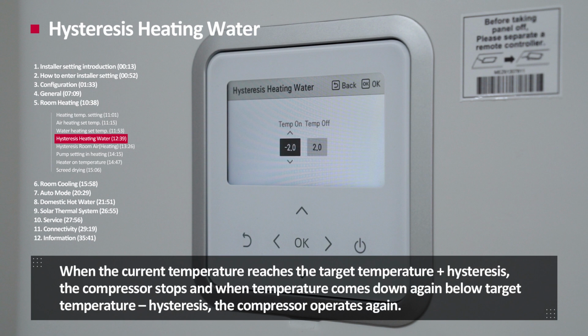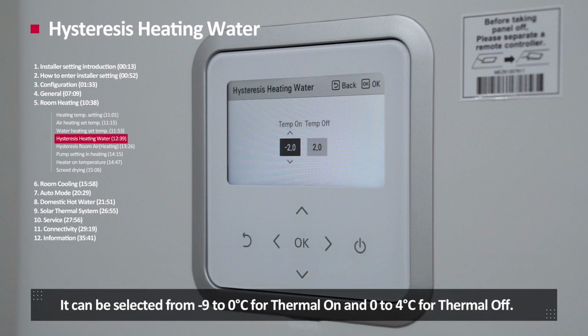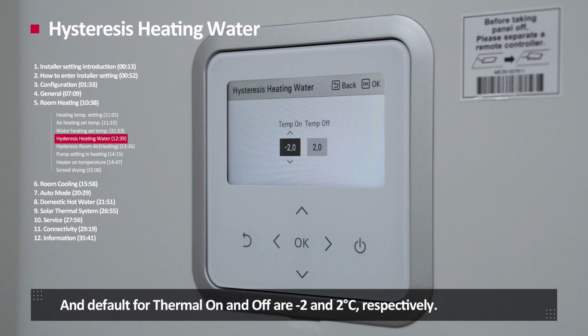When the current temperature reaches the target temperature plus hysteresis, the compressor stops. And when the temperature comes down again below the target temperature minus hysteresis, the compressor operates again. It can be selected from -9 to 0 degrees Celsius for Thermal On, and 0 to 4 degrees Celsius for Thermal Off. And default for Thermal On and off are -2 and 2 degrees Celsius respectively.